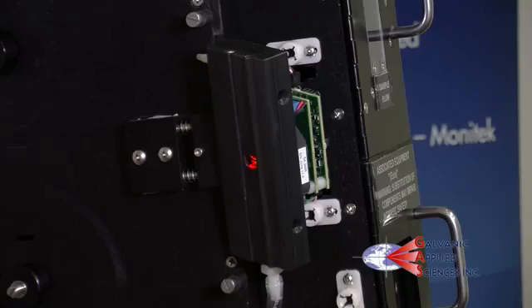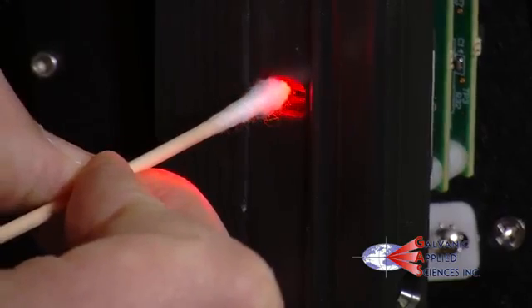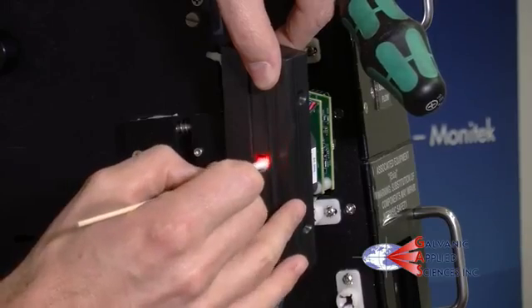With a q-tip or paper towel, clean the sample chamber opening by lightly wiping off any dust buildup which could interfere with the sample reading.